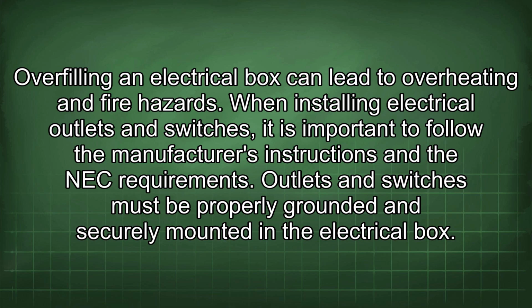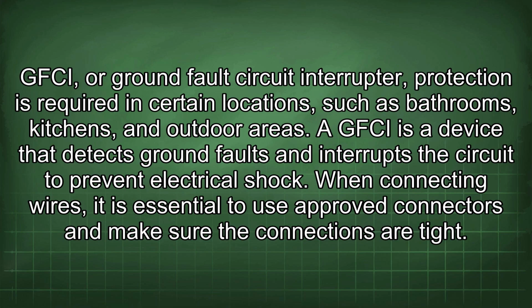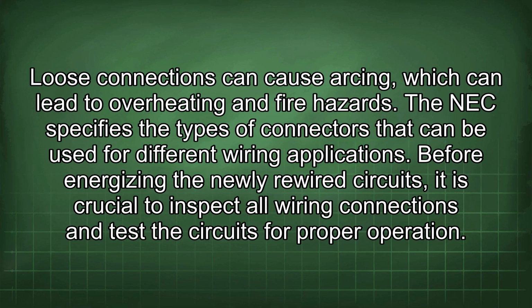When installing electrical outlets and switches, it is important to follow the manufacturer's instructions and the NEC requirements. Outlets and switches must be properly grounded and securely mounted in the electrical box. GFCI, or ground fault circuit interrupter, protection is required in certain locations, such as bathrooms, kitchens, and outdoor areas. A GFCI is a device that detects ground faults and interrupts the circuit to prevent electrical shock. When connecting wires, it is essential to use approved connectors and make sure the connections are tight. Loose connections can cause arcing, which can lead to overheating and fire hazards.